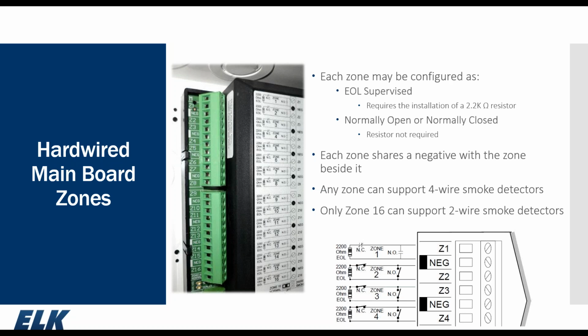The zones on an M1 system, each zone can be configured with the end-of-line resistor, which is a 2.2K, or they can be configured normally open or normally closed with no resistor required. That's optional per zone. That's not a global setting. Now, the purpose of the end-of-line resistor is to provide supervision of the wiring from the panel out to the device. So the resistor should be at the device itself for proper supervision of the loop. If it's not possible to get the resistor at the sensor, you can simply leave it out of the installation and configure the zone normally open or normally closed.